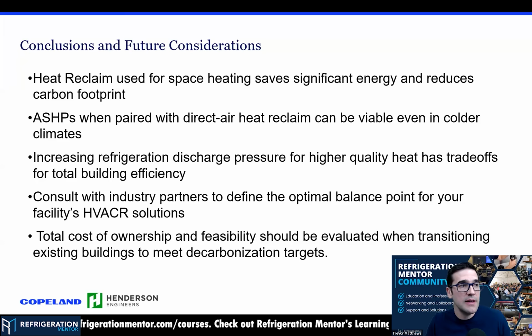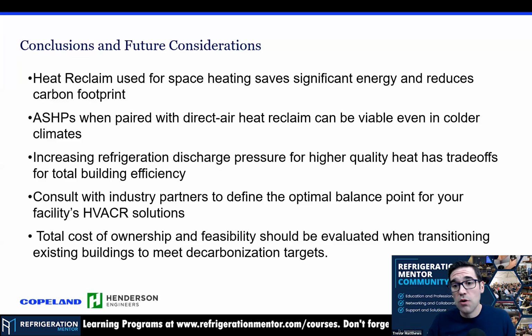Because at the end of the day, we see more and more adiabatic gas coolers going out there, but the problem is the total cost of ownership is more, because in your location you've got very bad water, you need more filters, you're by an airport and it's really dirty, so they've got to be changed way more than a place that isn't dirty.